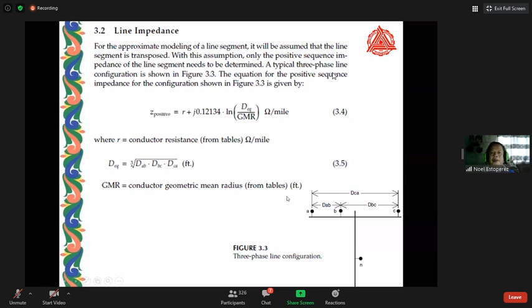We all know this from our power system analysis in determining the impedance of a line. Considering the configuration for our three-phase line, which is usually configured horizontally for our conductors, we come up with the equivalent, which is the cube root of DAB, DBC, and DCA. The GMR is the geometric mean radius, which can be determined from tables. Anyway, these are given, and we can determine this.